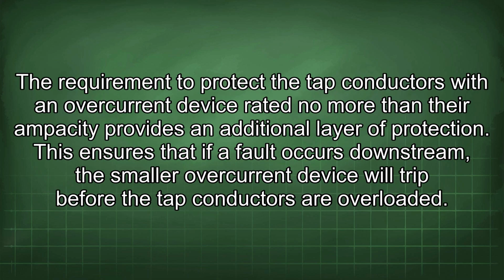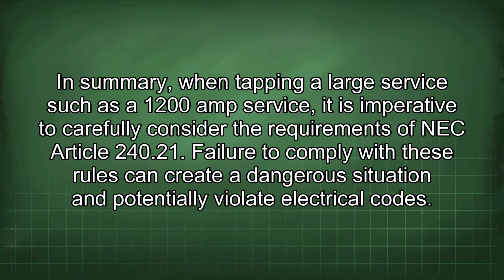The requirement to protect the tap conductors with an overcurrent device rated no more than their ampacity provides an additional layer of protection. This ensures that if a fault occurs downstream, the smaller overcurrent device will trip before the tap conductors are overloaded. In summary, when tapping a large service such as a 1200 amp service, it is imperative to carefully consider the requirements of NEC Article 240.21. Failure to comply with these rules can create a dangerous situation and potentially violate electrical codes.